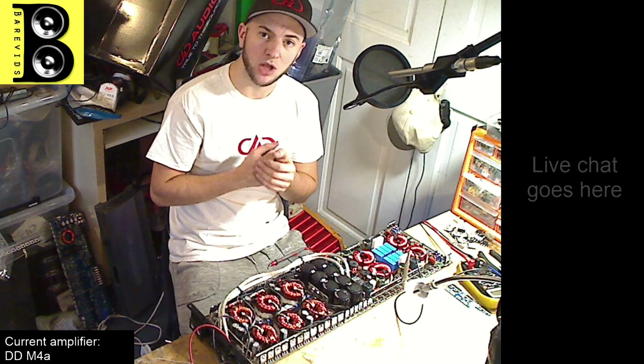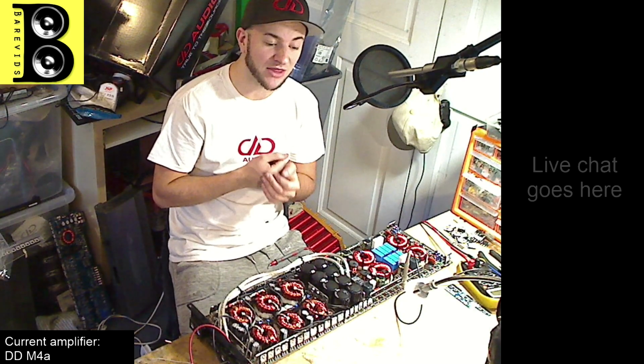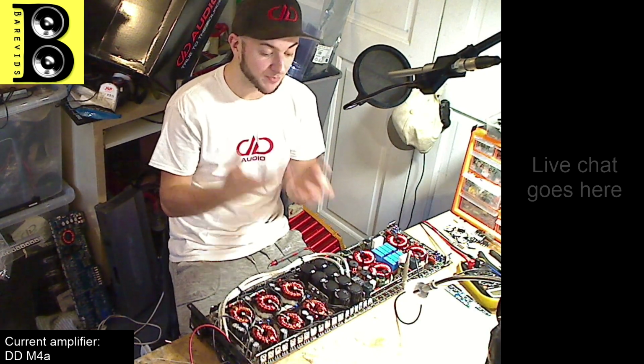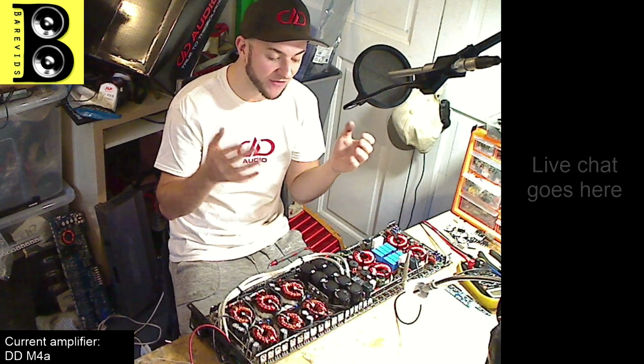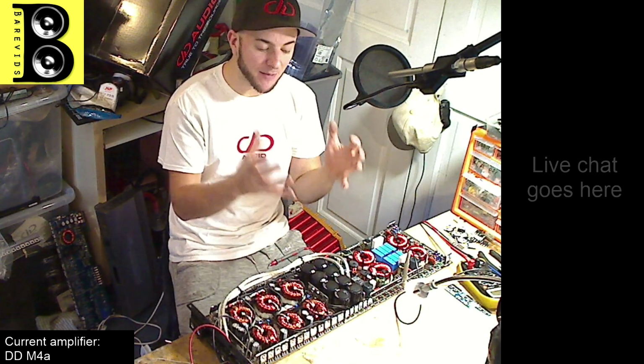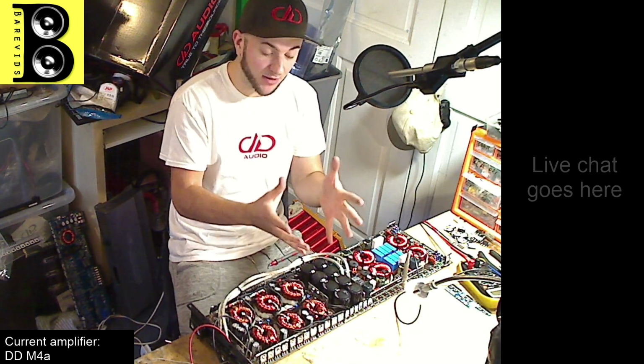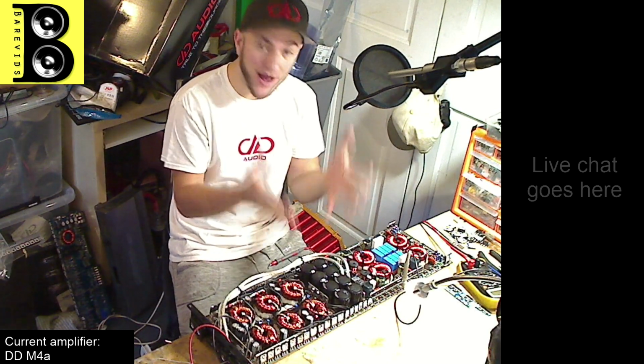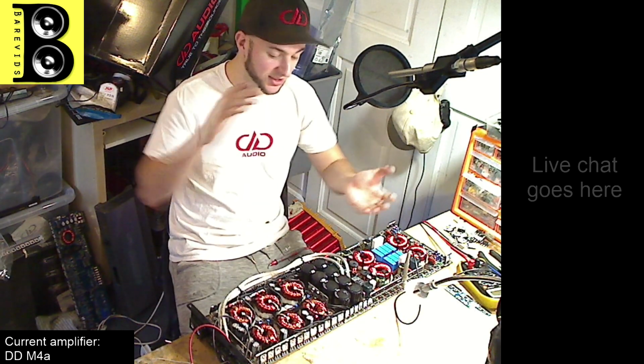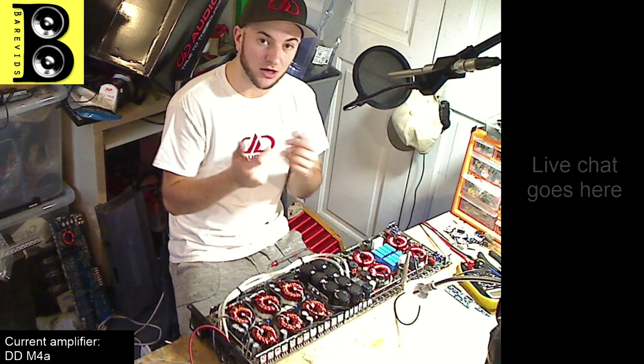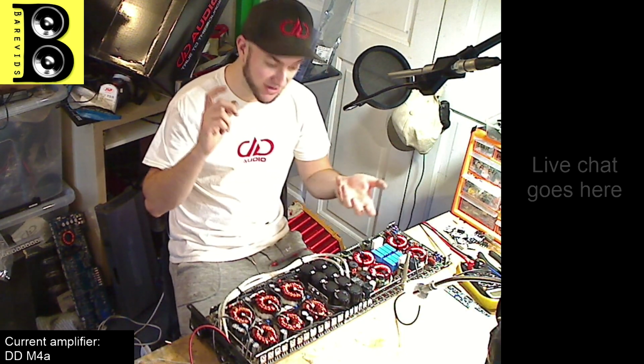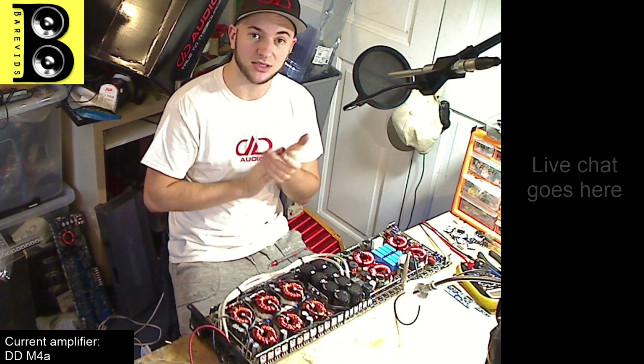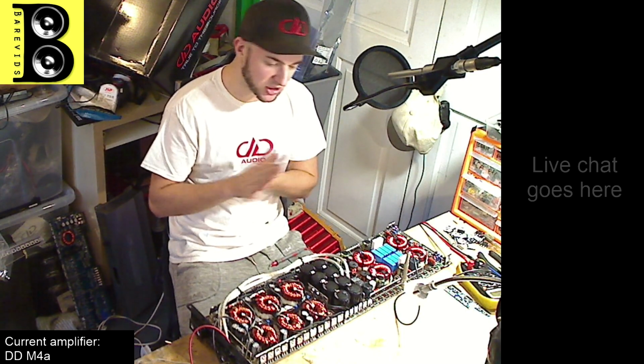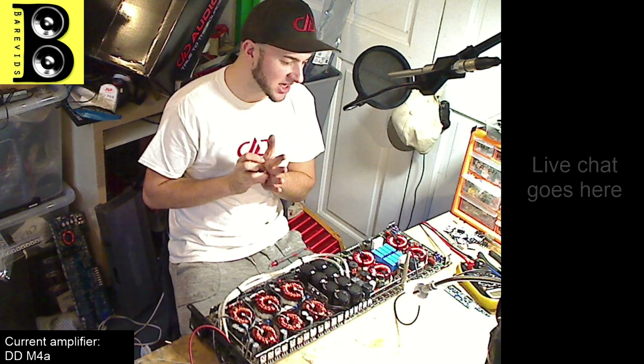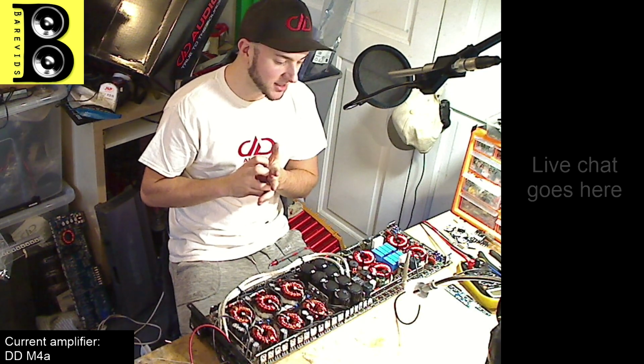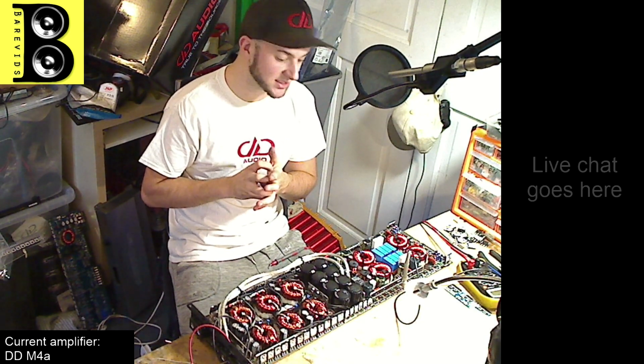If you use something too low in resistance, you'll get a spark and the resistor might explode, because you're basically dumping capacitors which have an incredibly high potential output current - their ability to output high current is immense, the internal resistance is nothing. So if you run a low-value resistor on these caps, it's going to get overloaded, get hot, maybe smoke up and explode. So just use a high value resistor to keep it within tolerance, and it'll get the rail voltage down to 0 nice and quick.